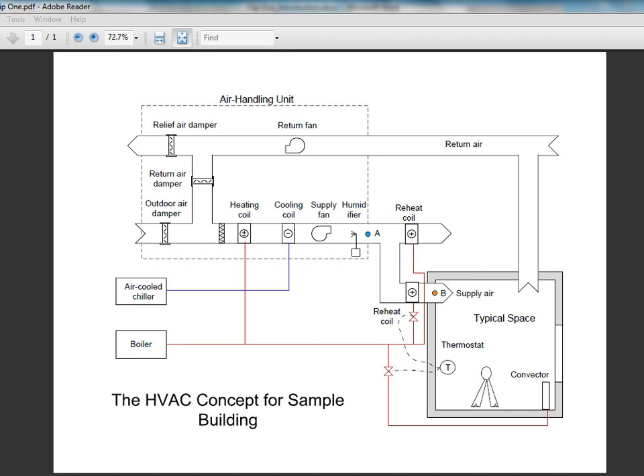This schematic represents a general air conditioning concept of the building, usually prepared at early stages of HVAC design by the project engineer. The concept determines the general arrangement and interaction of the HVAC equipment and sets forth the HVAC design scope. A central air handling unit, shown in the dashed rectangle, shall supply a constant volume of conditioned air to the occupied spaces via ductwork.